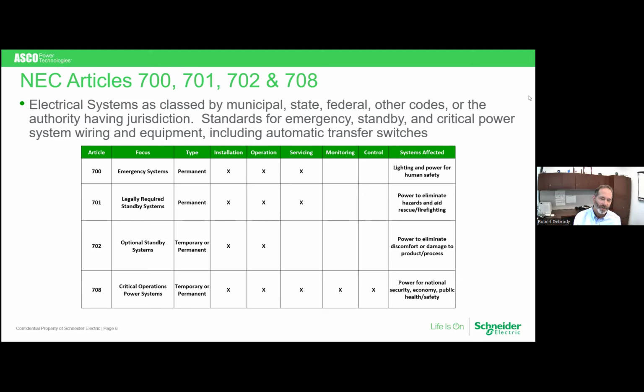For servicing, optional standby systems aren't addressed because you, as the owner of that backup power source, are responsible for following the manufacturer's instructions. I skipped the 'type' column—that refers to whether the backup power source is permanent or temporary. Emergency systems and legally required standby systems require a permanently installed backup power source on site. For optional systems, it can be temporary or permanent, whatever you choose.